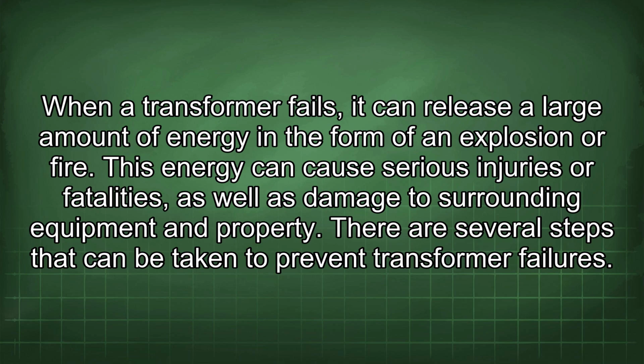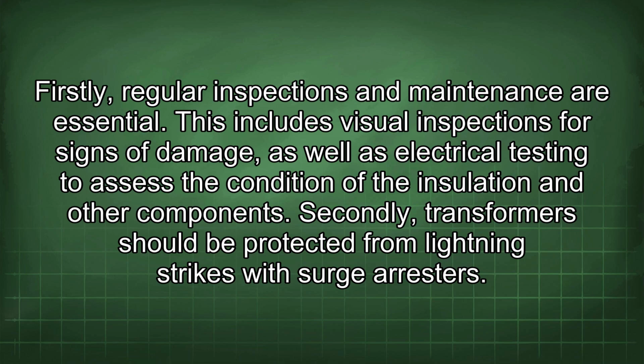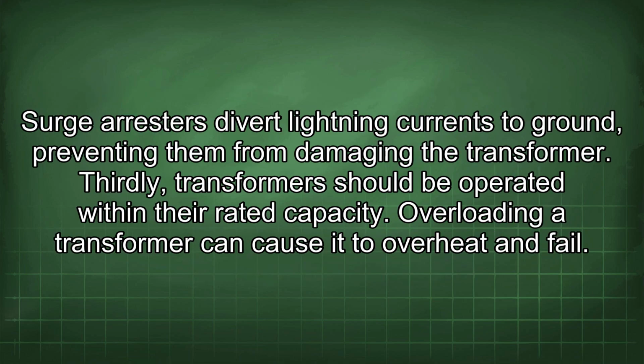There are several steps that can be taken to prevent transformer failures. Firstly, regular inspections and maintenance are essential. This includes visual inspections for signs of damage, as well as electrical testing to assess the condition of the insulation and other components. Secondly, transformers should be protected from lightning strikes with surge arresters. Surge arresters divert lightning currents to ground, preventing them from damaging the transformer.